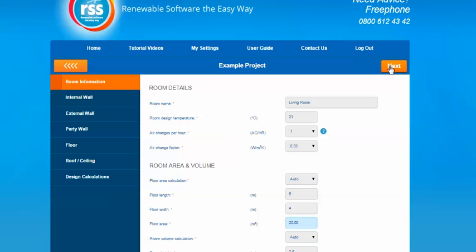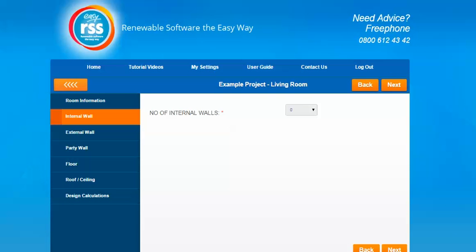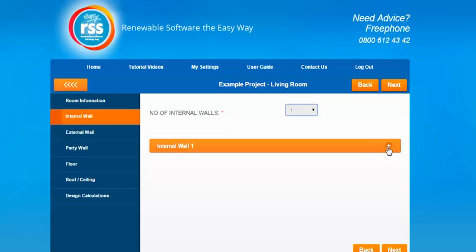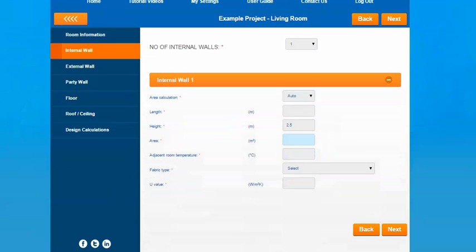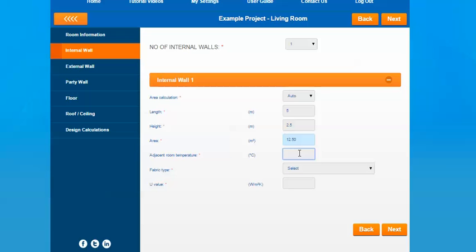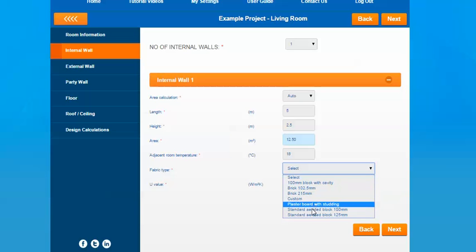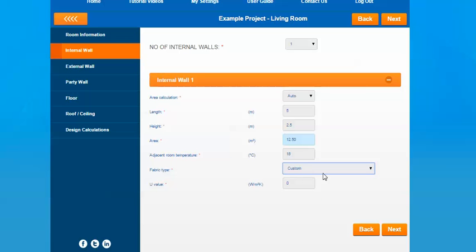Now we're on to the different elements of the room. The first section relates to the internal walls, so in this case we'll just put in an example of one internal wall. It'll give you options to put in the length of the wall, and again you have a manual option to input the area directly. You then have an option to input the adjacent room temperature — this accounts for any heat loss into the adjacent room if it's set at a lower temperature. We'll put in an 18 degree temperature for the adjacent room. You then have an option to select the fabric type; there are some options already inputted or you can choose custom to input your own U-value. If you select one that's already provided it'll complete the U-value for you.